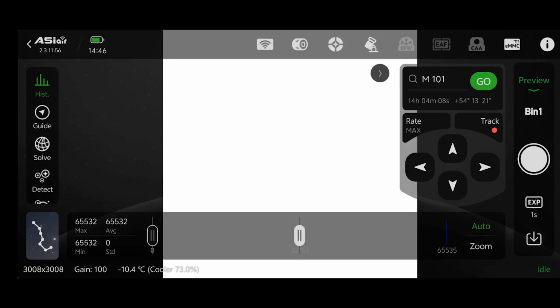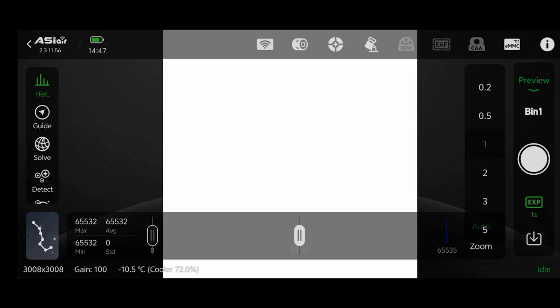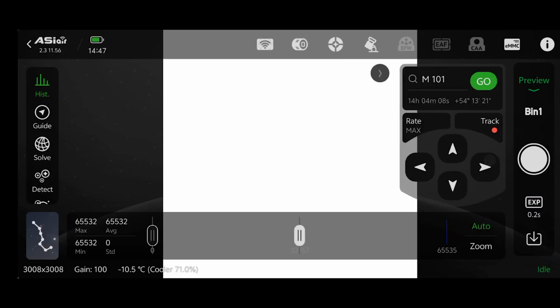As you can see, the minimum of the histogram is 0 and the maximum is 65,535, which is the max for this camera. I need to get that to a third of it, so between 22,000 and 25,000 or 26,000. So I reduce the exposure time to 0.2 seconds.